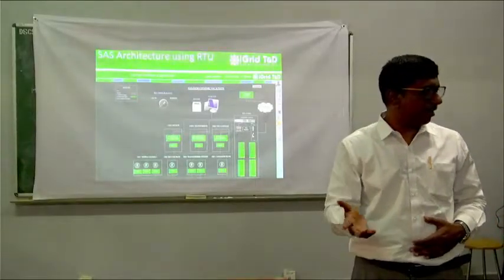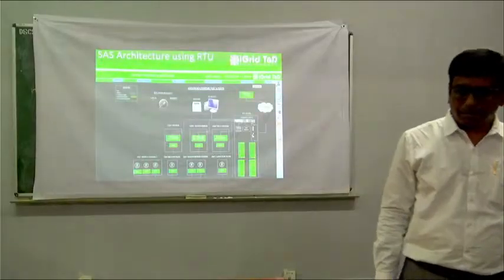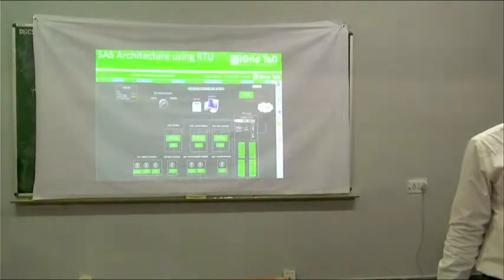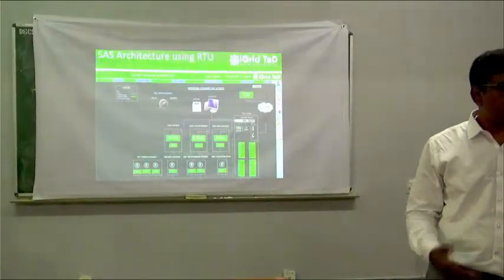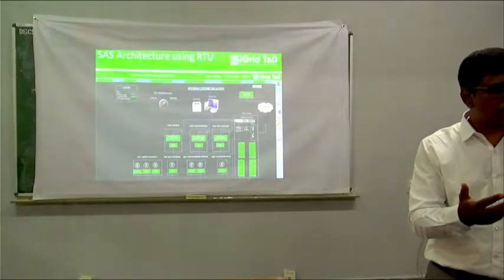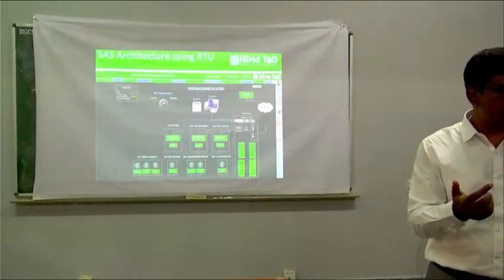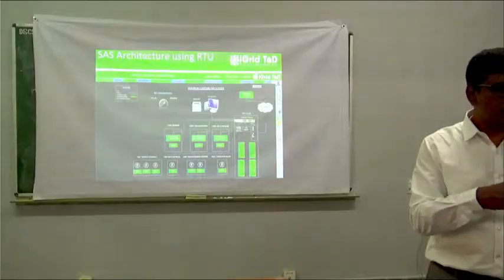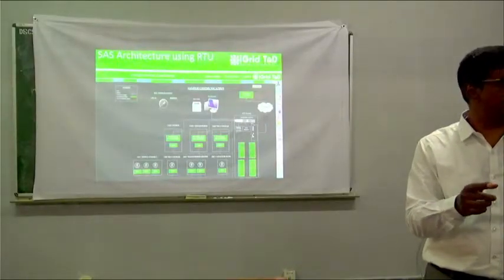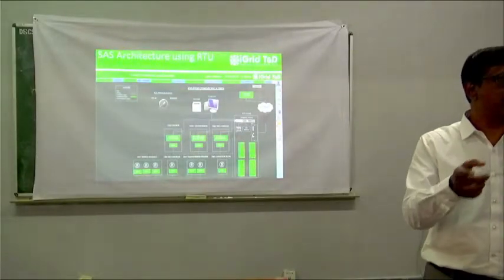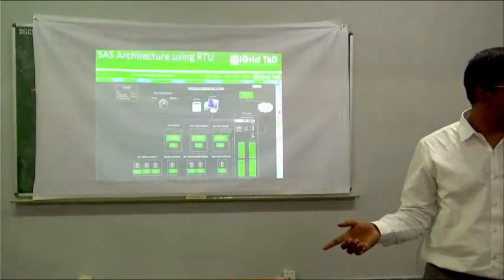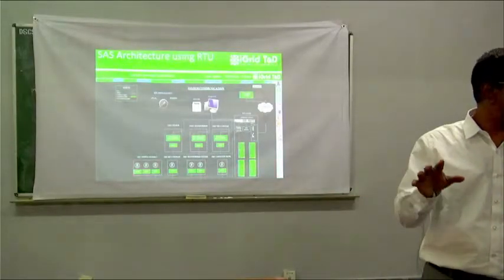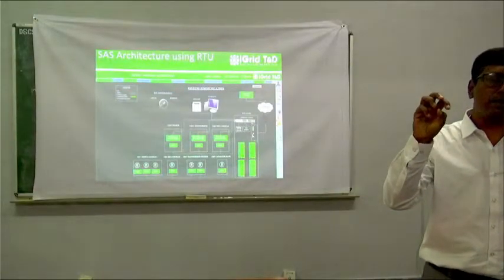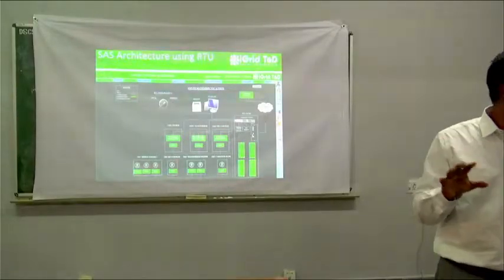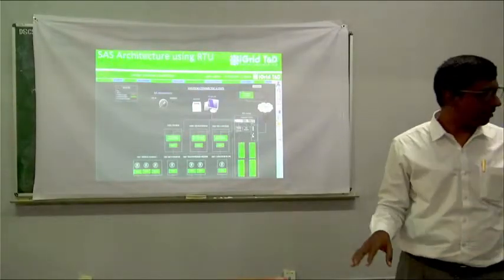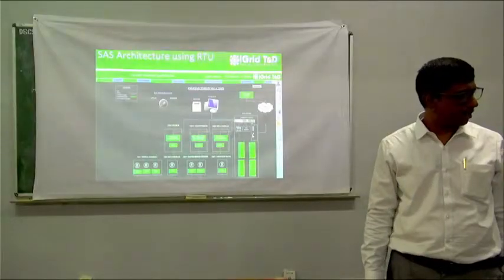Okay. Am I clear why we use RTUs? Okay. So it means it takes the data from the panel and will display it. Correct. Basically, it is going to scan the breaker status, all those things. You have your NO/NC contacts in your breaker, which would have been brought to the panel. From the panel, I am going to take it and give it to this. And this I am going to show in an SLD, which helps me identify the status of my breaker and the status of my isolator, all those things. So this will not do any control action.